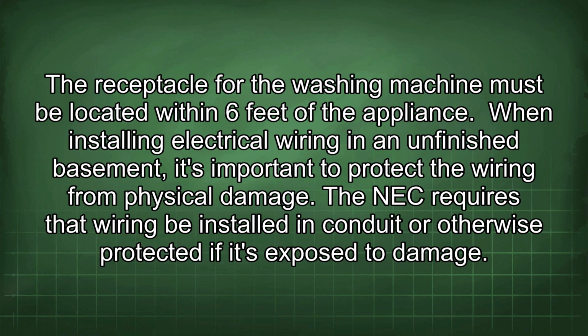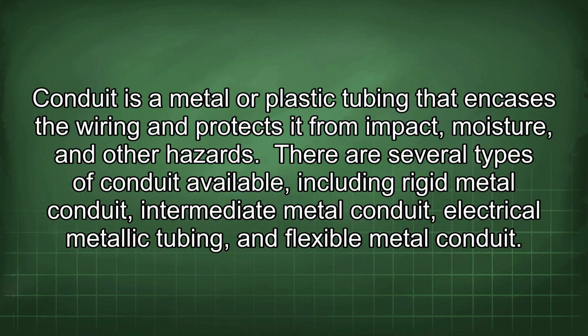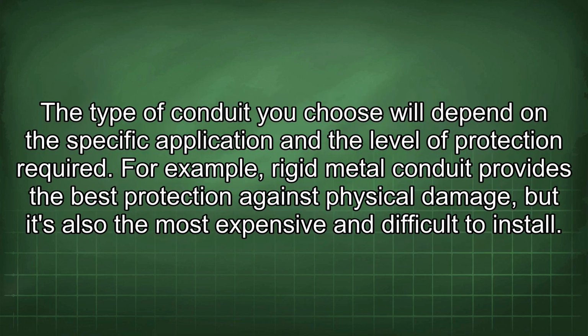When installing electrical wiring in an unfinished basement, it's important to protect the wiring from physical damage. The NEC requires that wiring be installed in conduit or otherwise protected if it's exposed to damage. Conduit is a metal or plastic tubing that encases the wiring and protects it from impact, moisture, and other hazards. There are several types of conduit available, including rigid metal conduit, intermediate metal conduit, electrical metallic tubing, and flexible metal conduit. The type of conduit you choose will depend on the specific application and the level of protection required. For example, rigid metal conduit provides the best protection against physical damage, but it's also the most expensive and difficult to install.